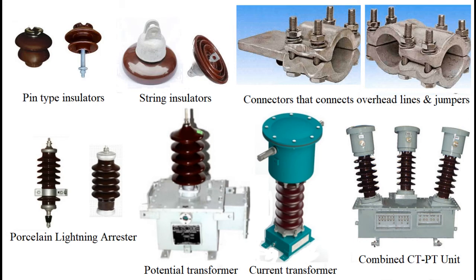For connecting two hanging overhead conductors, a pin insulator is required to give support to jumpers. Jumpers are short-length overhead conductors that are connected to the actual overhead lines through clamps or connectors. If the pole structure consists of four poles, then the structure of overhead conductors is created between two pairs of poles. This structure is identical for each phase of all three phases. When jumpers pass through the groove provided for jumpers, the direction of the groove may be rotated while fitting on the channel to keep the jumper in a tight position.